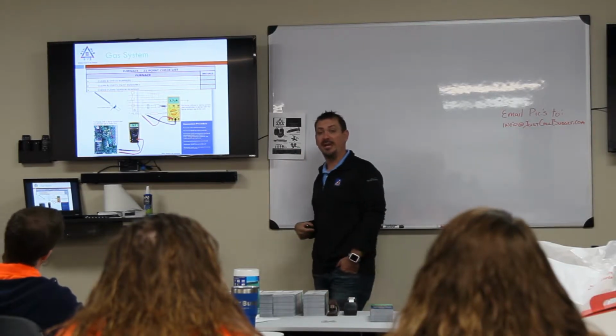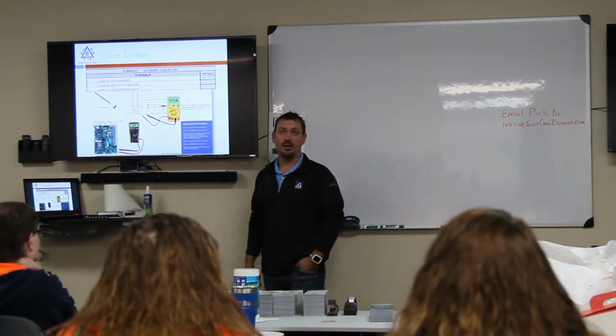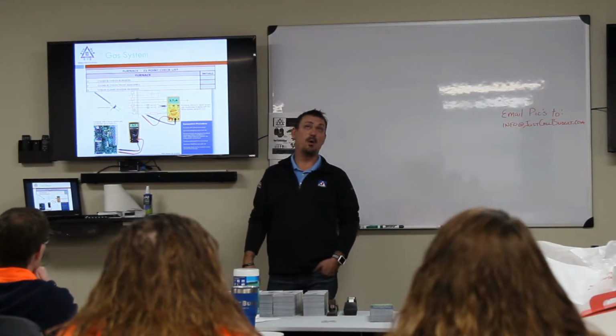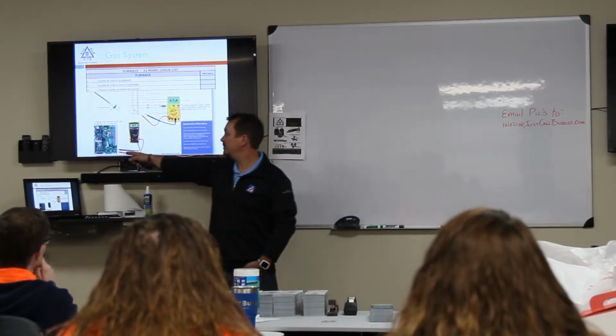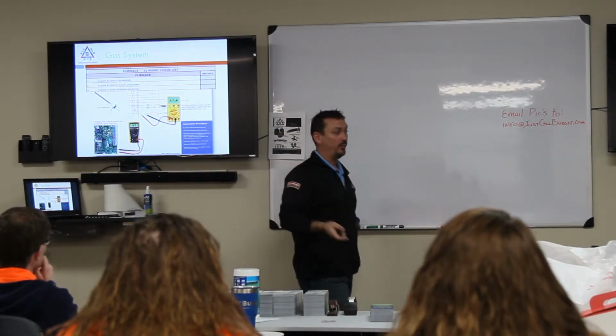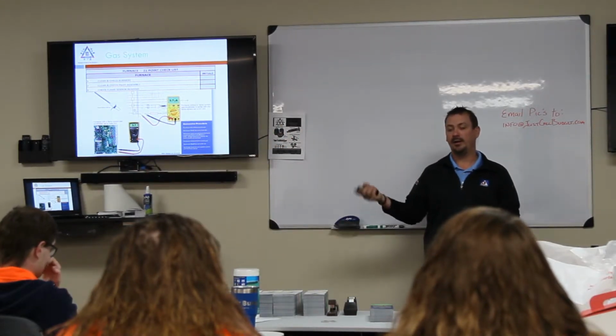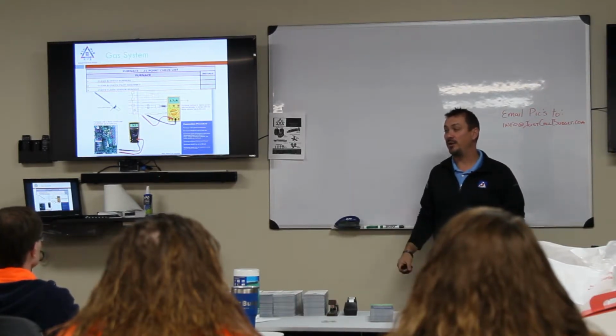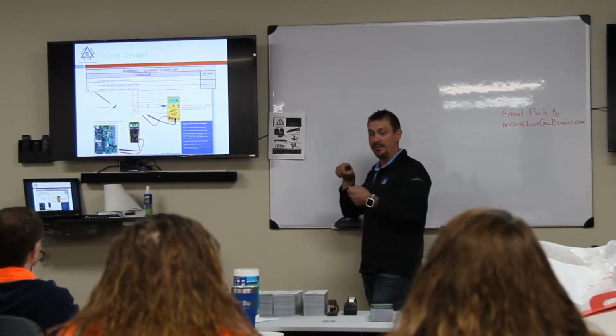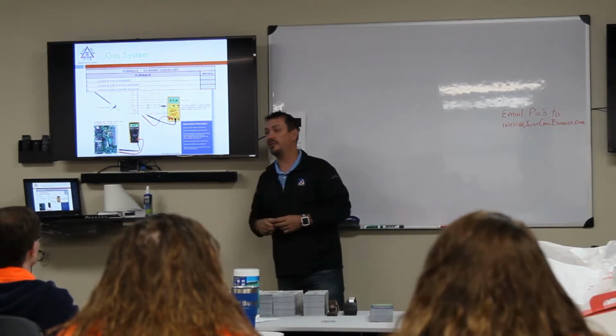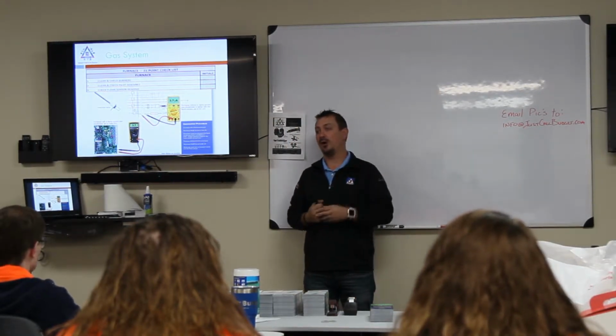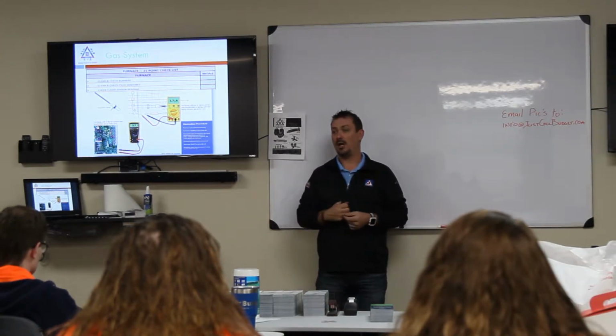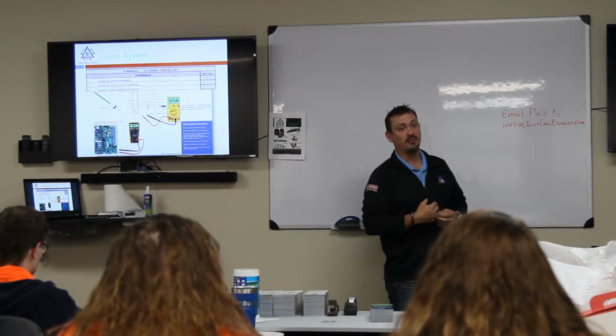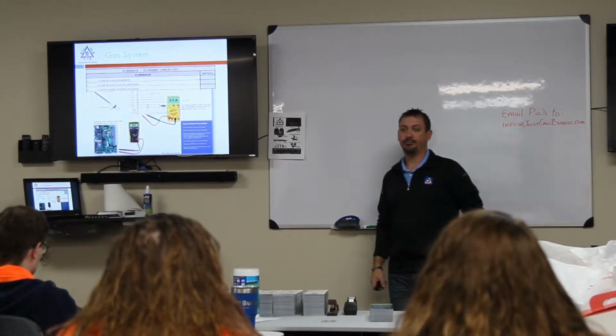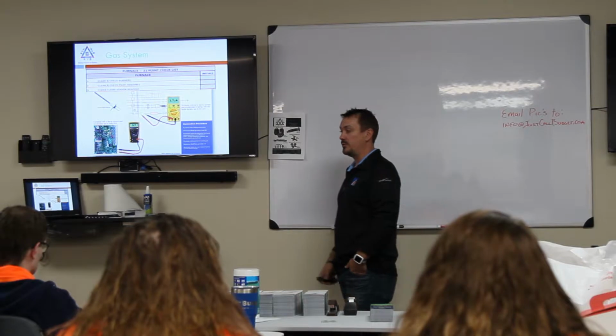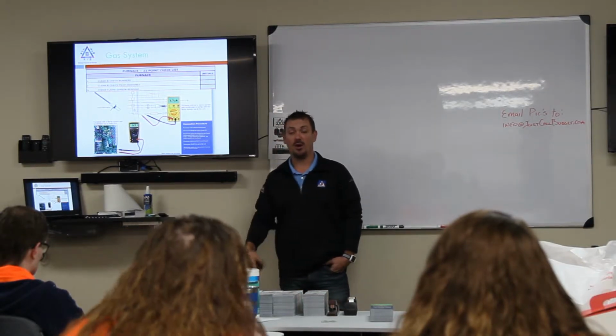A lot of control boards today, especially the Texas Instrument control boards, and now White Rogers is also putting a flame current sensing pad on there. Most of the Coleman and York units have the flame current sensing pad on them, so it makes it really easy for you to go up and take your leads and put them on there. You're going to be checking volts DC. 1 volt DC equals 1 microamp, so you're going to get the same reading that you're going to look for, which is above 1.5, to 4, 3, 3.5, something like that. It's a good signal to see on a flame sensor.